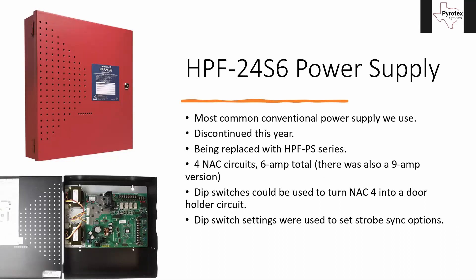The bottom two terminals are your sync signal — that's where your sync would go. This panel requires a separate sync signal from your input signal. There are some conventional power supplies where it'll duplicate whatever signal is sent into the input, so if you've got a synced NAC coming in you just land it on the input and it'll duplicate it — but this was not one of those. This one required dip switch settings to tell it what to do with the sync; if you didn't tell it to follow the sync coming in, then it just wouldn't do it.